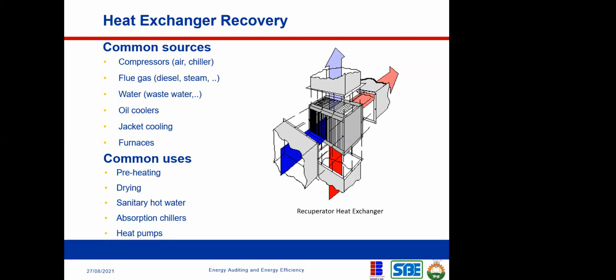I don't know if you have actually noticed how hot your compressors could be, whether the one on your fridge, your freezer, or your air conditioning system. Compressors are generally hot. So for industrial application, they are good places to recover heat. Okay. So another one is flue gas. Flue gas means gas that is leaving your exhaust pipe from your generator or from your burner. Okay. So that's a flue gas.